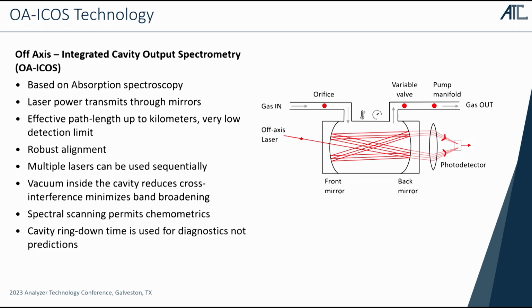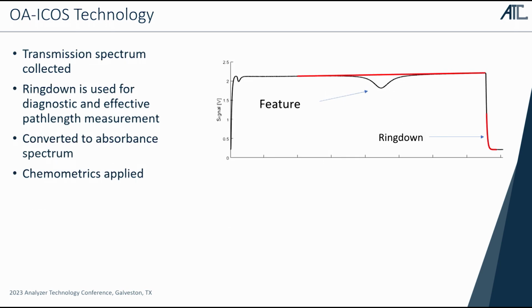There's only 2 repeat slides, but basically we bring light in from a laser. It bleeds through the back of a parabolic mirror. It bounces off the mirror several times. We get kilometers of path length. And as it's bouncing off of the mirrors, the back mirror, there's a detector, optics, it goes onto a detector, and some of that light's bleeding through. So we're collecting the sample as the laser is bouncing back and forth through the cell.